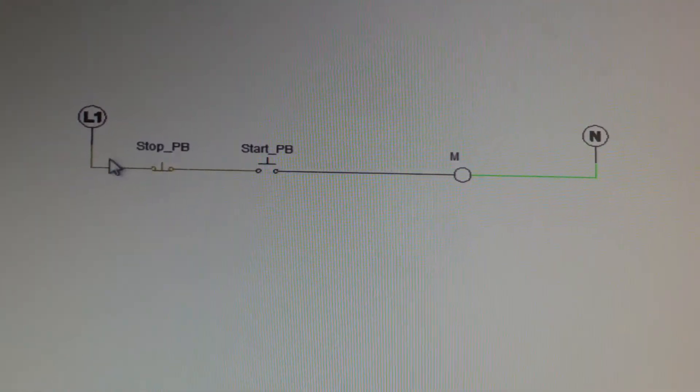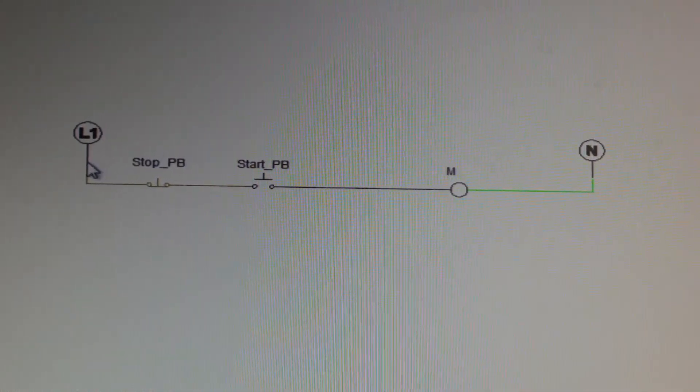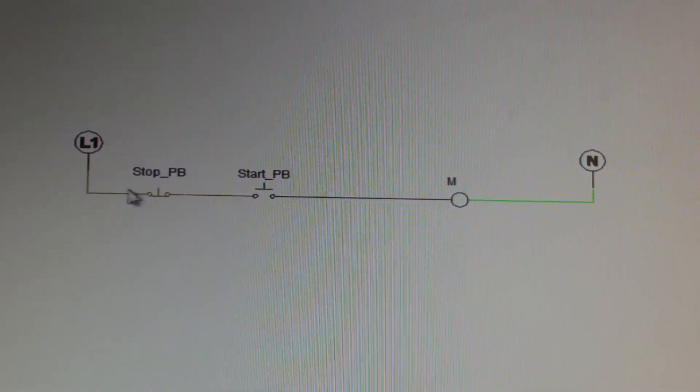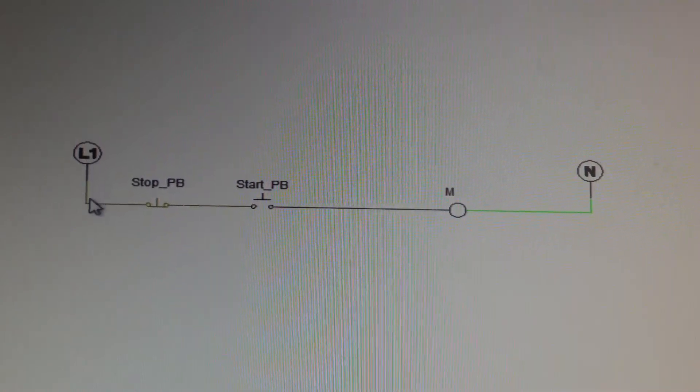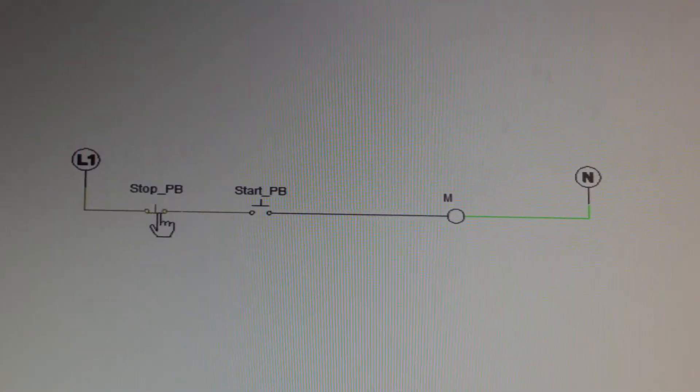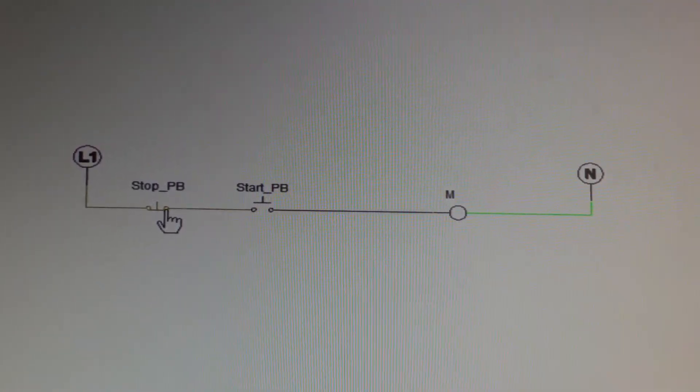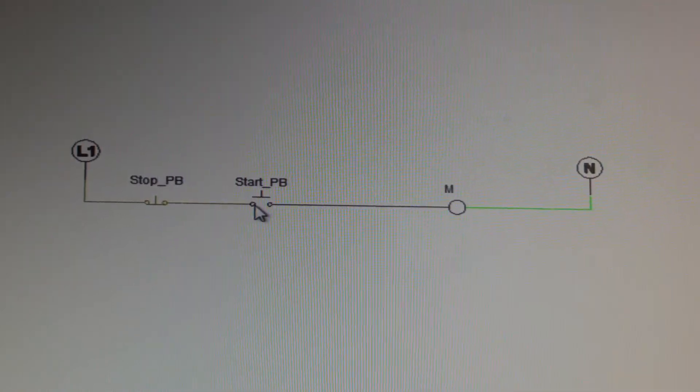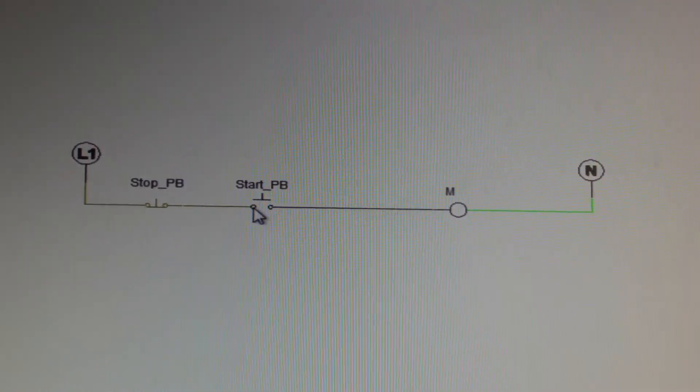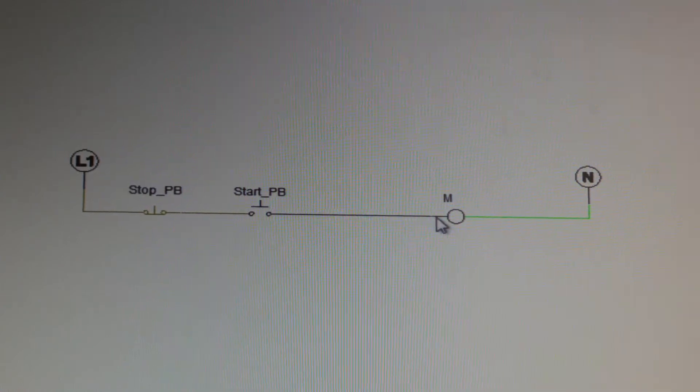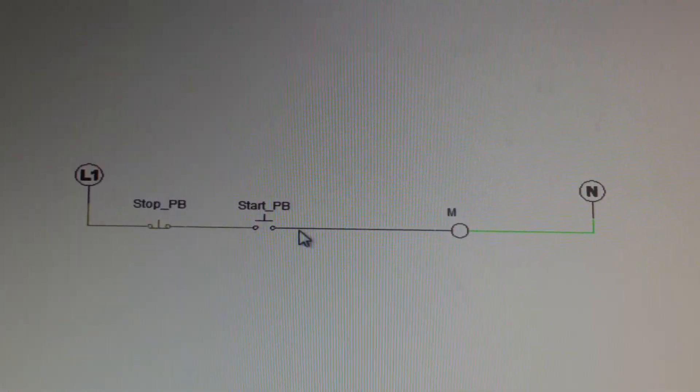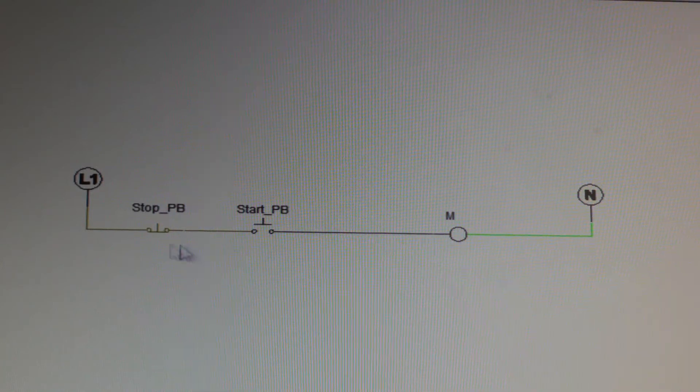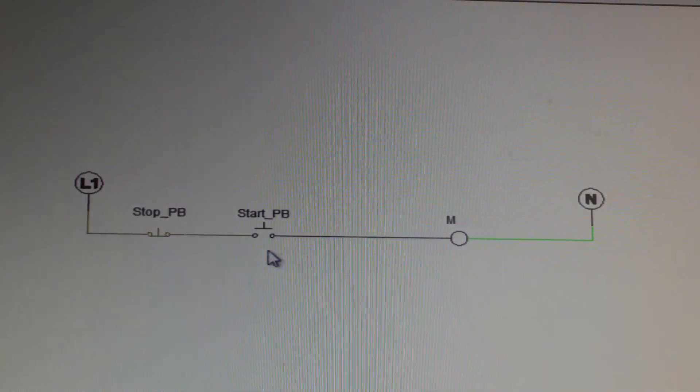So let me demonstrate. I know it's hard to see in the video, but this is green. So right now this tells me that L1 is providing current through the stop button, which is wired normally closed, and is sitting here at start PB. On the other side of start PB, it's black. So it's telling me that this current is not the same on the other side. So the flow is stopped at this point.